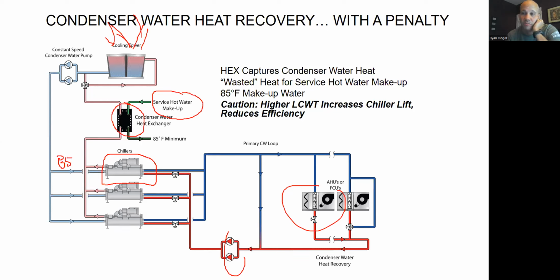But if I'm going to use this as makeup water for my service, my domestic water coming from the city in the middle of the winter, it's probably like 50 degrees, right? So this is 50-degree water coming in, right?